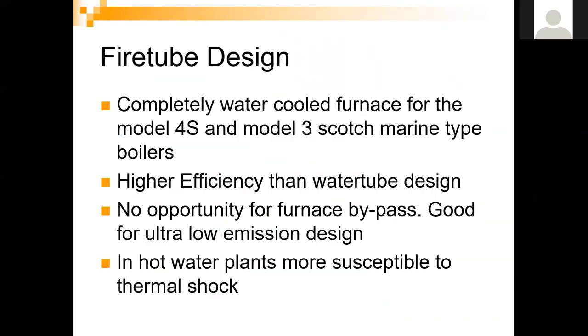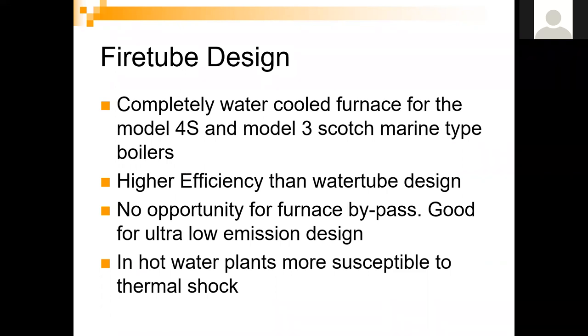Advantages of a fire tube boiler: completely water-cooled furnace, typically higher efficiency than a water tube design, no opportunity for furnace bypass — which is great for ultra-low emissions design — and tubes sealed at the tube sheets on either end. One downside: in a hot water plant with a 500 horsepower boiler, tubes are about 20 feet long. If varying return water temperatures are sent into that boiler, those fixed tubes start to expand and contract — potentially an inch on either side — causing thermal shock. You must be careful not to thermally shock the boiler and create leaks.